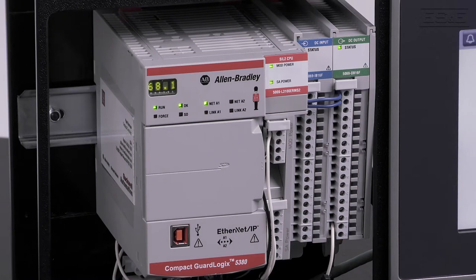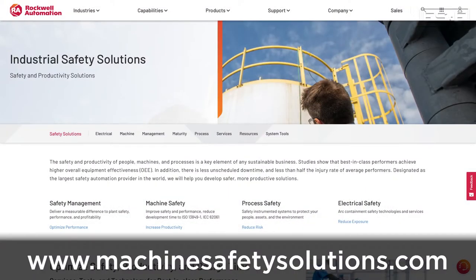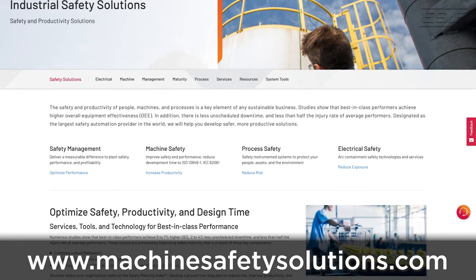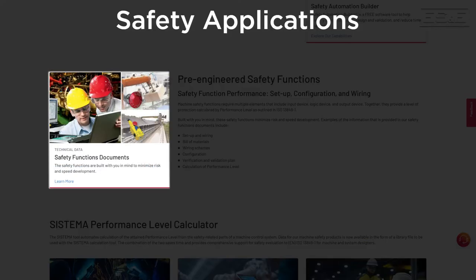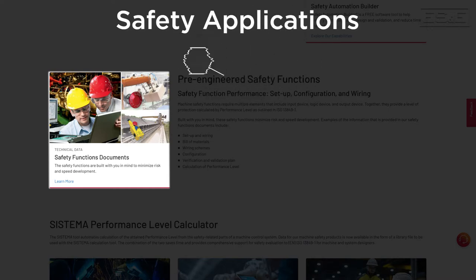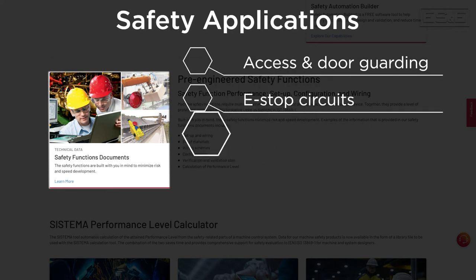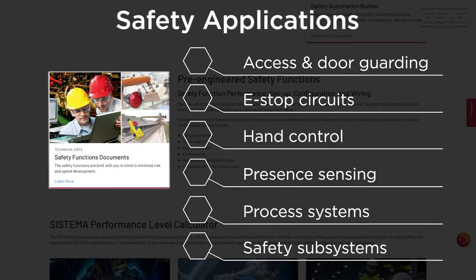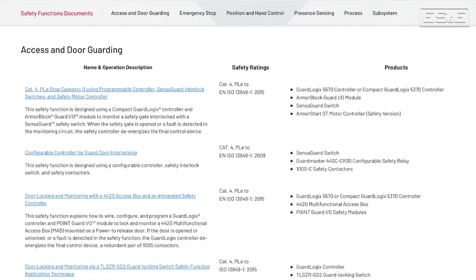The first advantage of utilizing Rockwell GuardLogix controllers are the pre-written safety applications. These can be found on the web at MachineSafetySolutions.com, which is a Rockwell webpage that archives what they call safety applications. Safety applications are documents provided by Rockwell that cover many safety functions such as access and door guarding, e-stop circuits, hand control, presence sensing, process systems, and safety subsystems. The applications contain the performance level achieved along with the category ratings and bill of materials used with component SIL ratings.